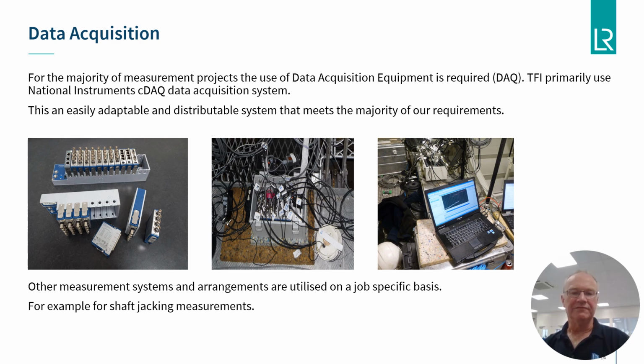Various input modules are available, however the most commonly utilised by TFI are voltage, IEPE for vibration and noise measurements, and strain input modules. The picture on the left in the laboratory shows the various chassis and modules for the different measurement types. The chassis can accommodate either 1, 8 or 14 input modules.